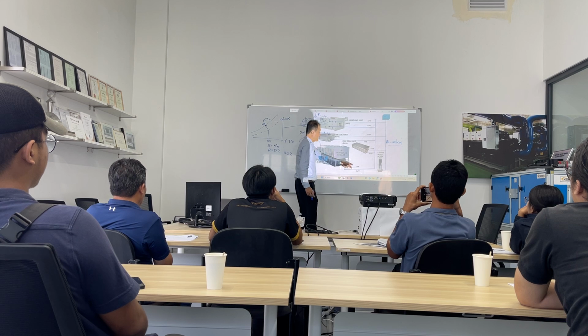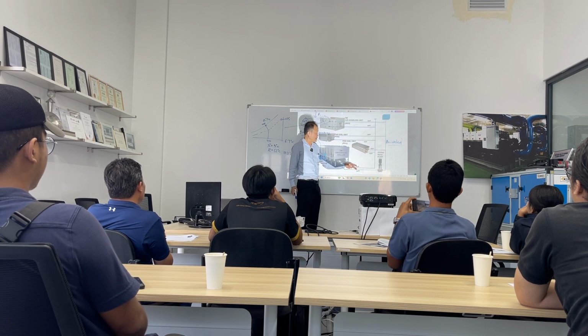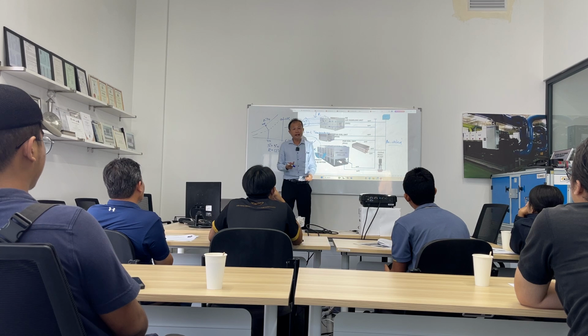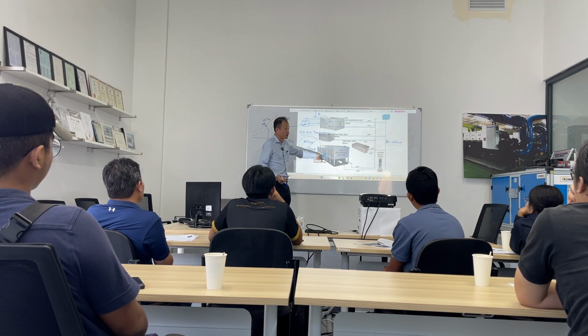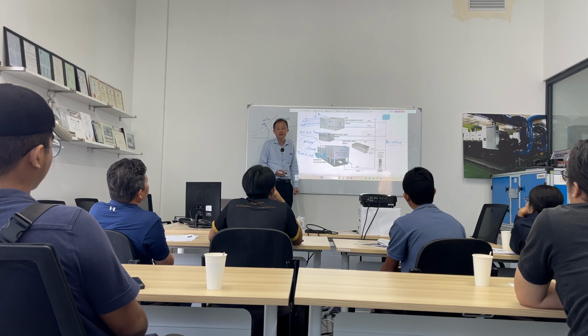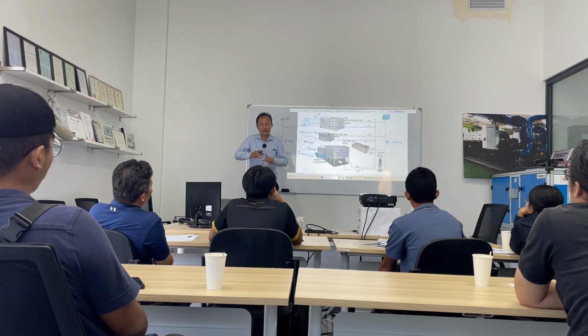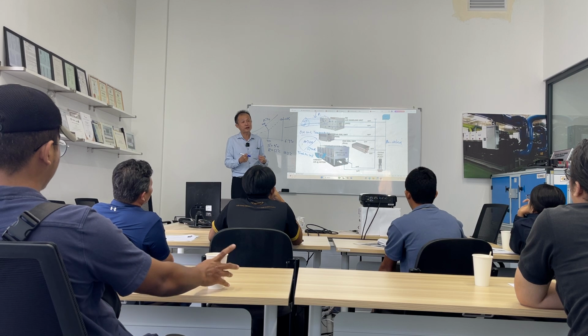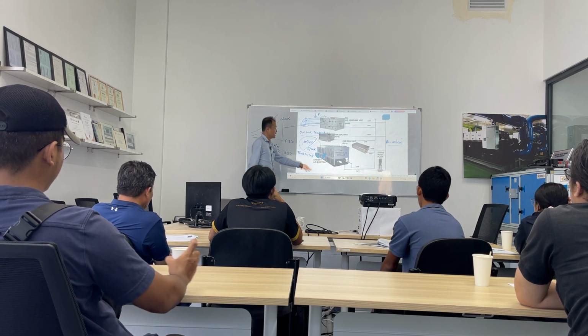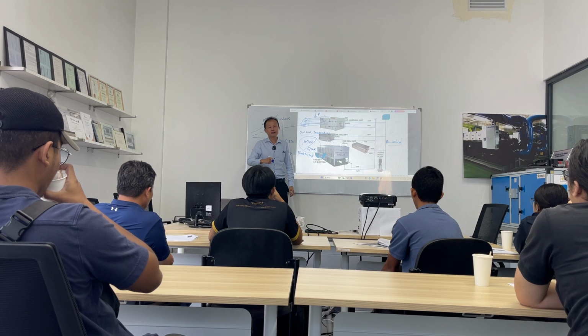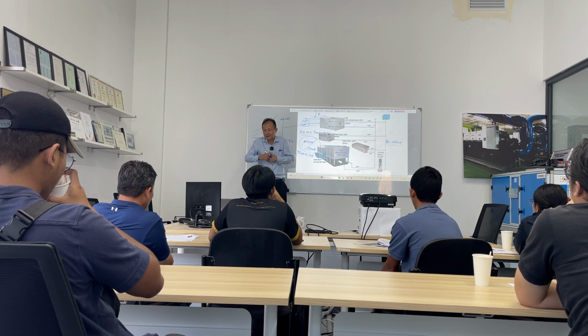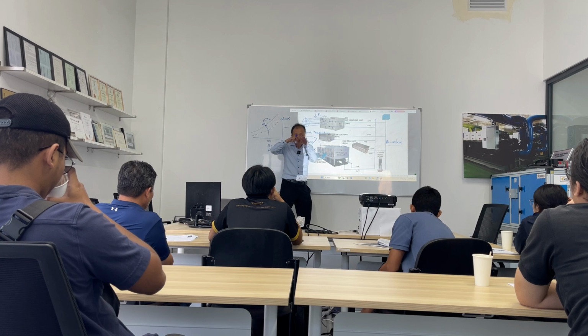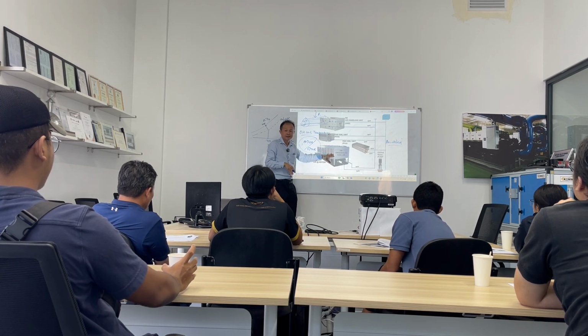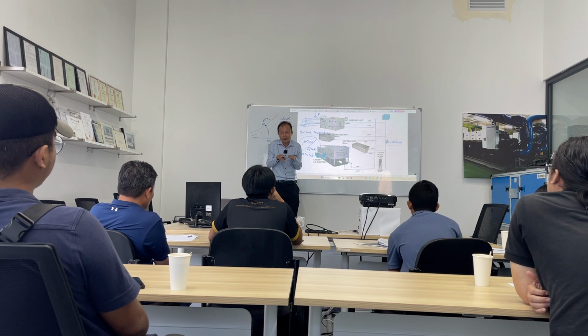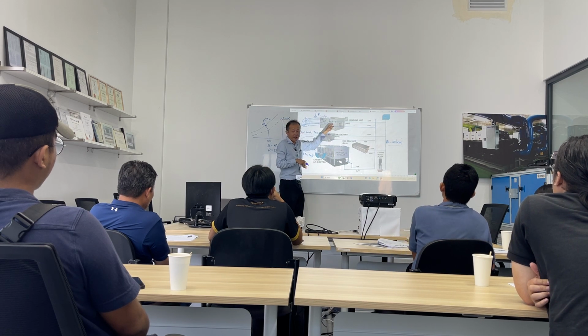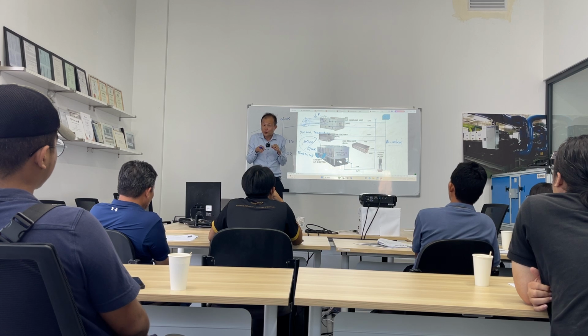Meaning that if I bring down this temperature, the air can be cooled much faster, but the compressor is actually working harder. So I don't want that, because the compressor is the biggest component that consumes the most power in the chill water system, right? Let's say in the past, a lot of laboratory tests have been carried out already. So this is the middle level temperature, where the chiller runs comfortably, not too hot, compressor not too hot, and the air is also cooled very effectively.